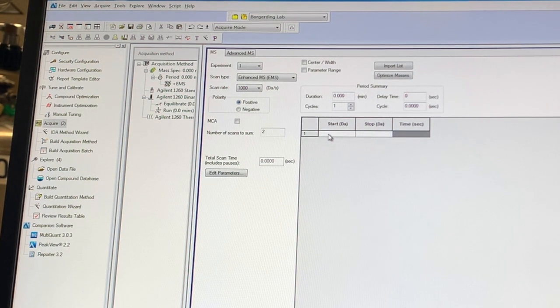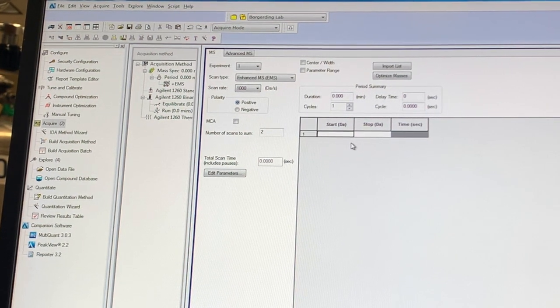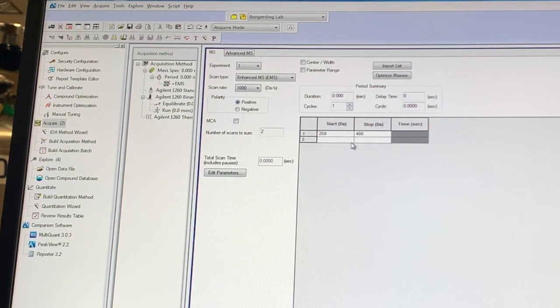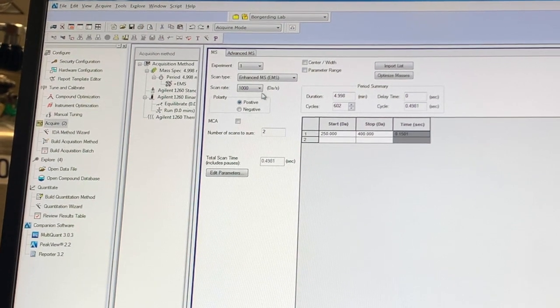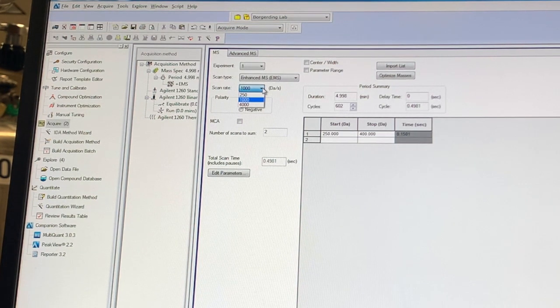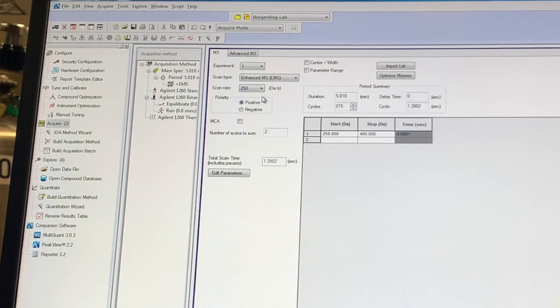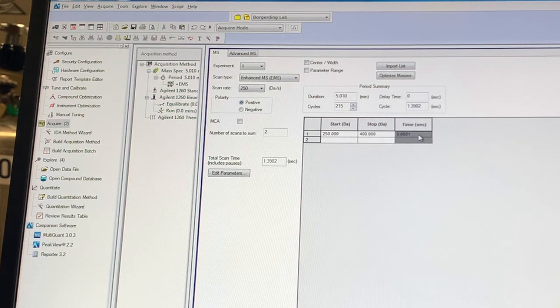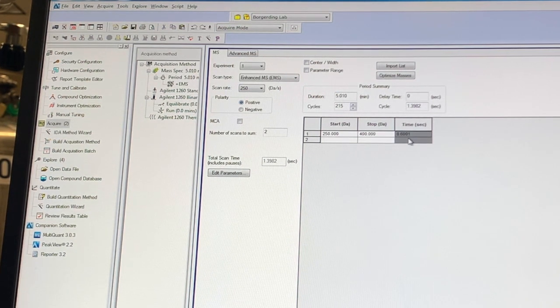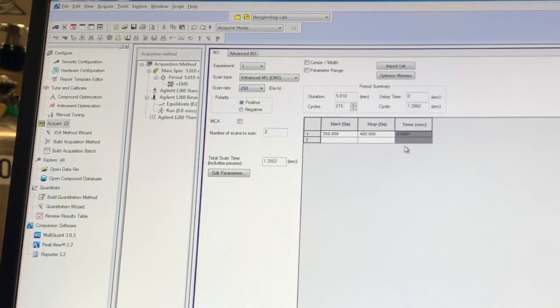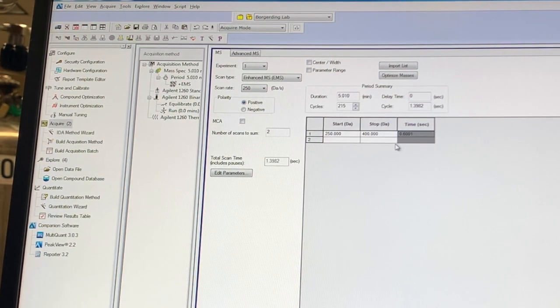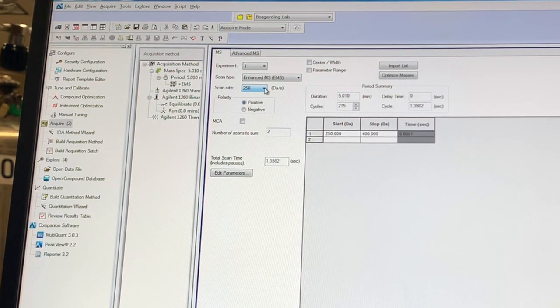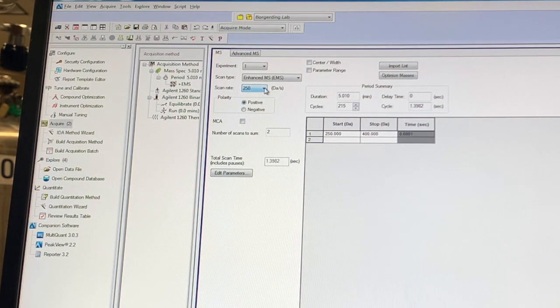And here, all we have to predefine is a range of masses. So we can say we want to detect 250 to 400 Daltons. And then the other parameter that we can change here is scan rate. And let's move that down to 250 Daltons per second. You typically want the time for each, so this cell here shows the time that it will take the method to scan this range given the scan rate, and we typically want that to be under one second. But you can get some better looking chromatographic traces if you use a slower scan rate because the mass spectrometer will be set on each given mass for a little bit longer.